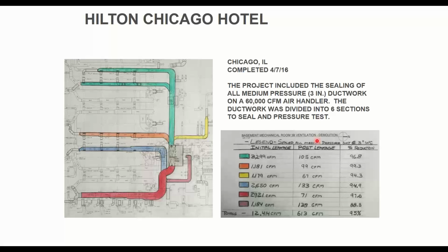But it was a pretty big system. It's a 60,000 CFM air handler, which is obviously large, in the Chicago Hilton Hotel. All the ductwork goes underneath the floors, and it's inaccessible, which makes things hard, obviously. It's going under all the banquet spaces. But initial leakage when tested was 12,000 CFM of leakage for this one air handler, which is obviously horrific.